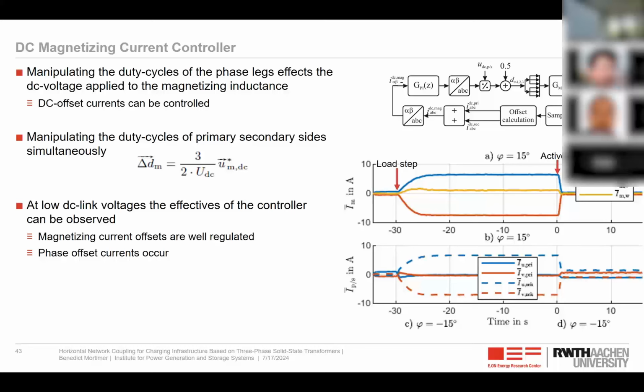Then you see how nicely the magnetizing DC components build up. So you actually see this is quite a slow phenomenon because it's only related to the time constant of the transformer. And here at t equals 0, we activate the controller, and as you can see, we can well regulate the magnetizing DC offset to 0.